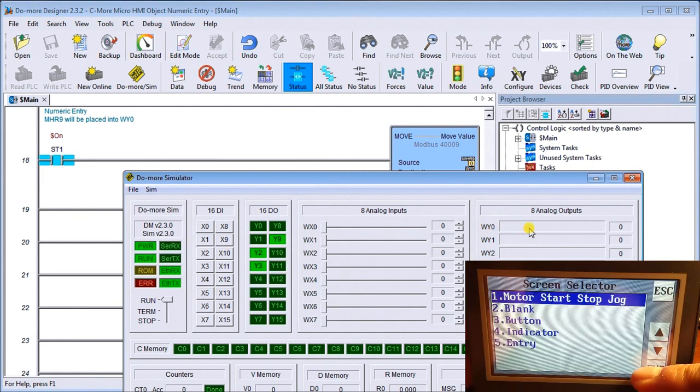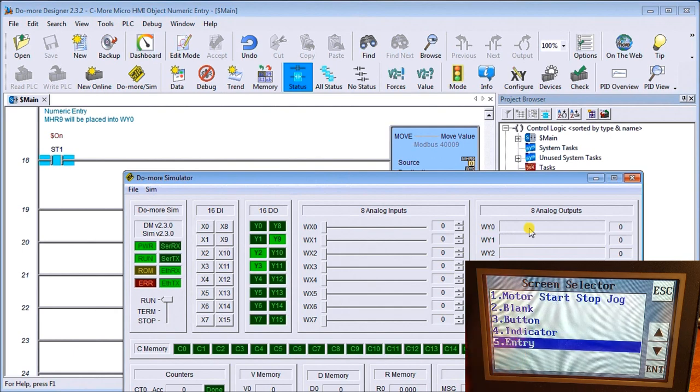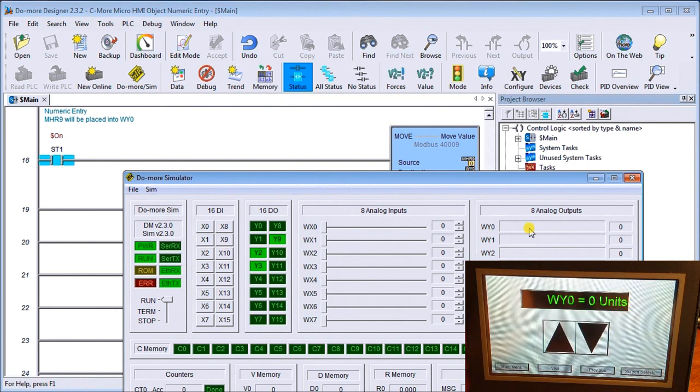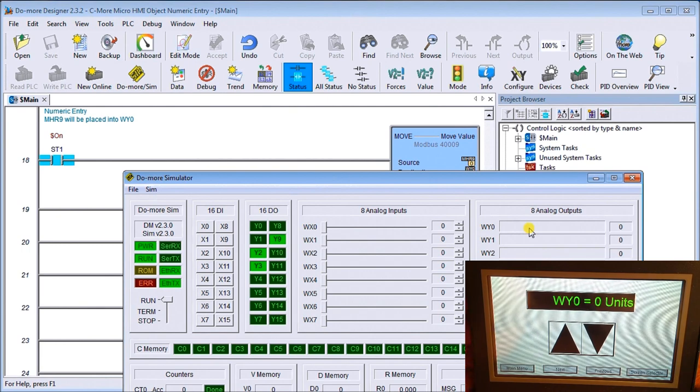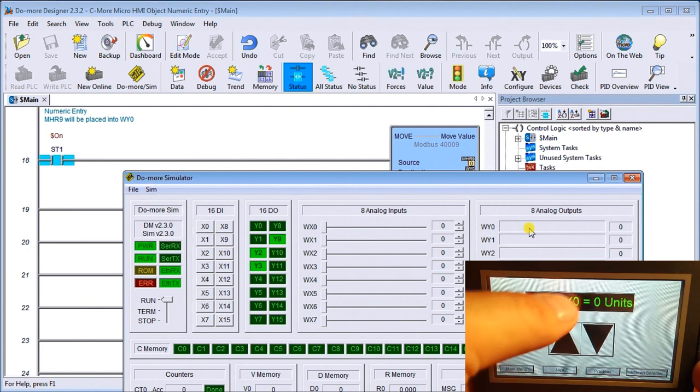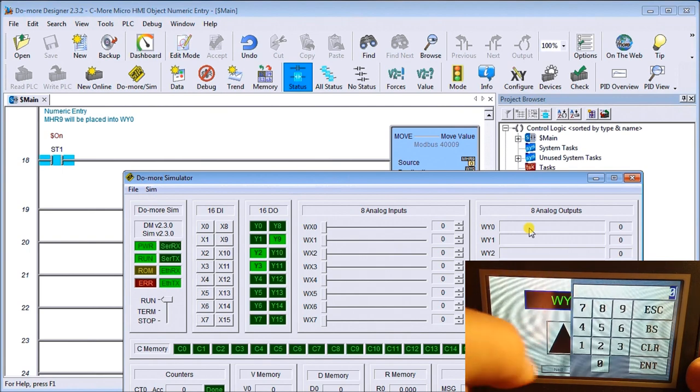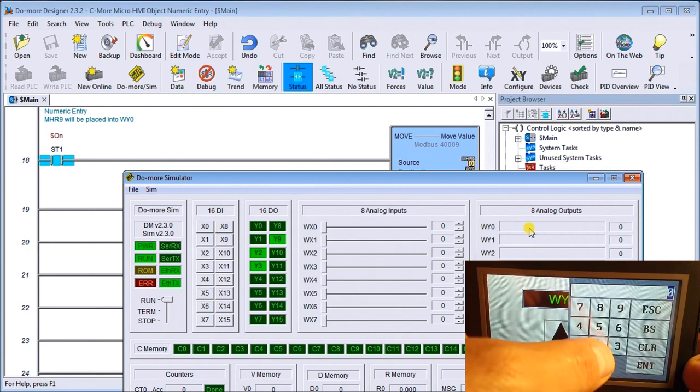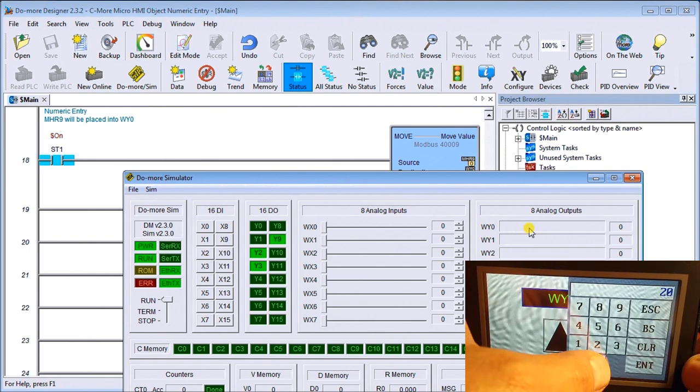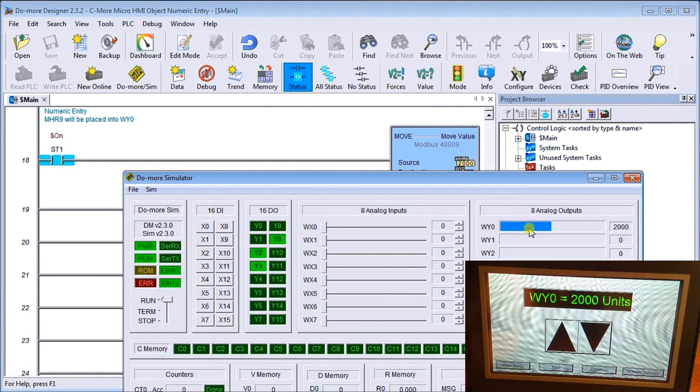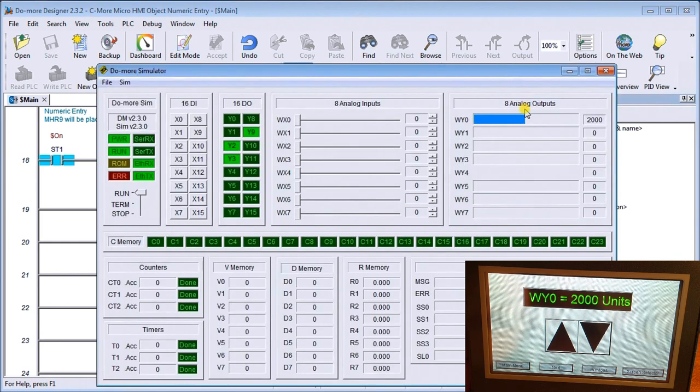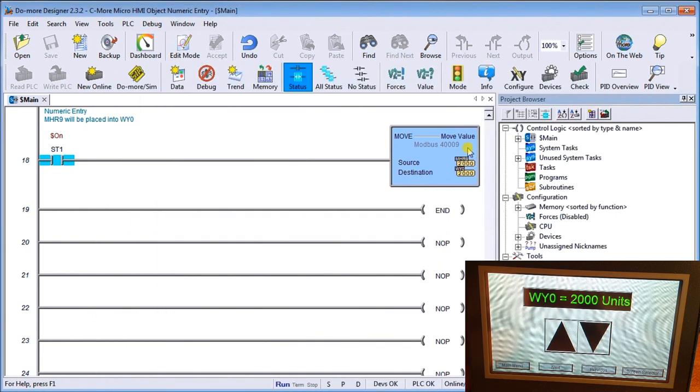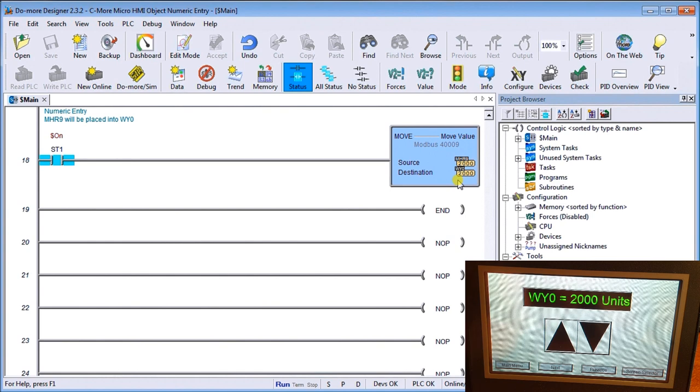On my screen we'll go to it. We'll hit page select, put entry, enter, and this is the one we just programmed. If we hit our units, we can enter a value. We'll enter the value 2000, enter. And what you'll notice is that up on my simulator we have the value 2000 that we've just entered. And if we actually look at my program, you can see my 2000 in MHR9 is being transferred to WY0 register.